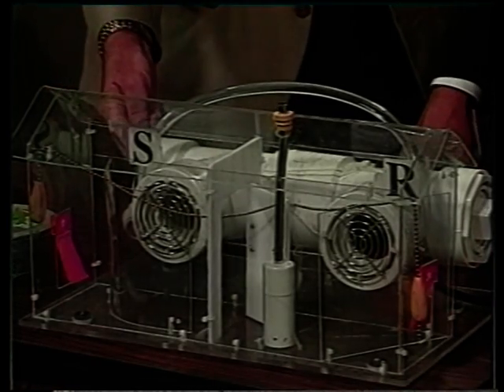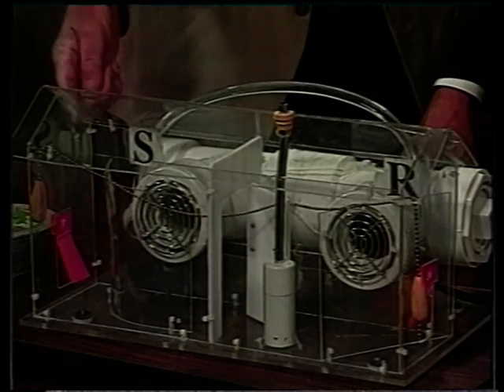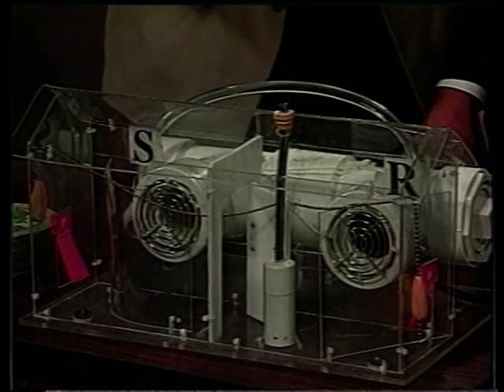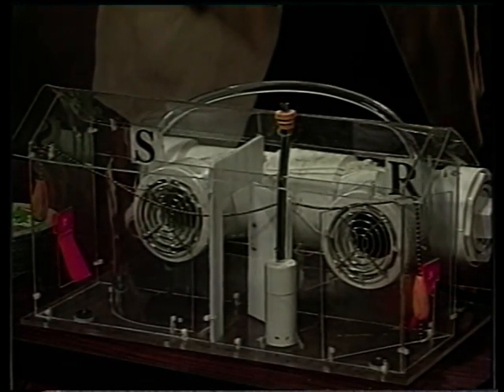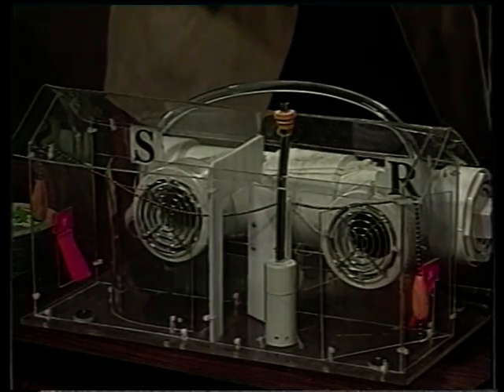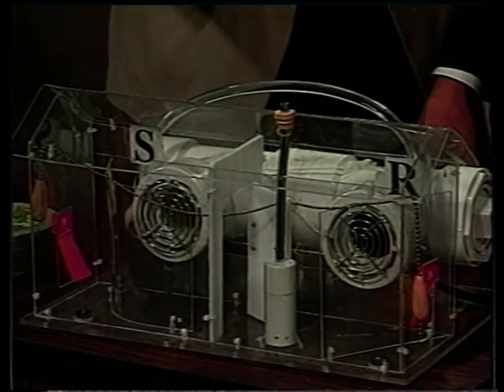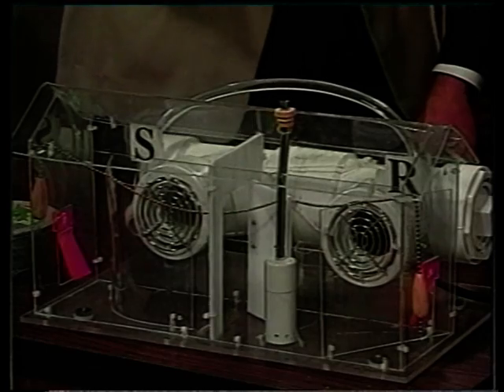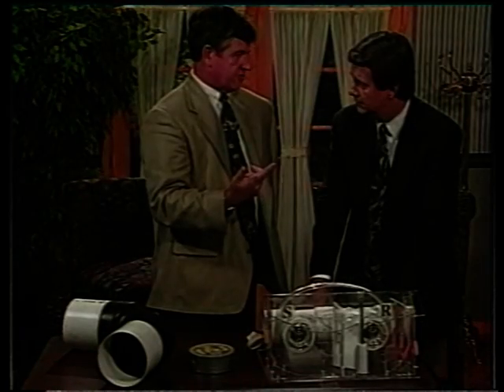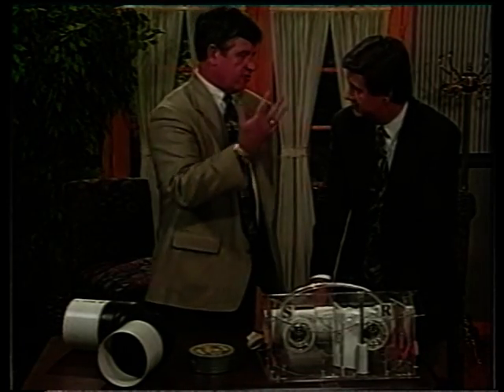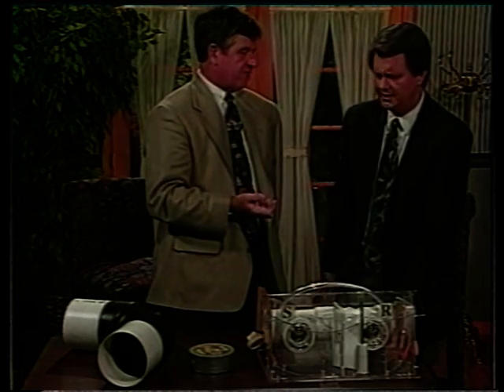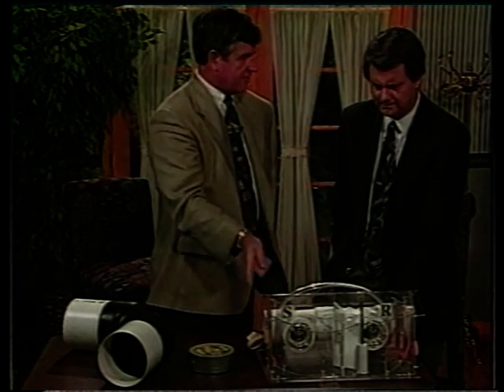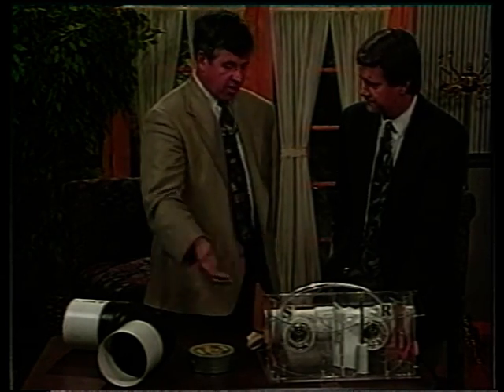So any leakage in the supply ductwork means the house now has to suck air in everywhere it can—but that's hot, humid air today, and in the wintertime it's cold air. That's why I can take a 2,000 square foot house and use a 1.5-ton cooling system on it, while most people put in a 3 or 3.5-ton system, because of these leakage problems they didn't solve—you've got to oversize it to offset that.